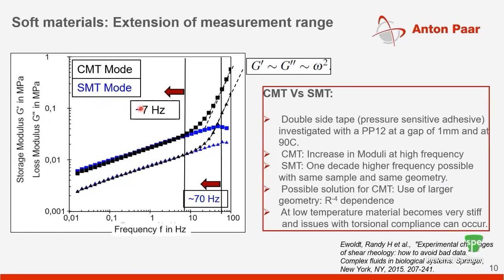And if you take a look at the black data, which is in the CMT mode, you will be tempted to interpret a curious power law scaling in the data. If you look at this increase in modulus as you increase frequency. But one needs to be careful because we know that this data at high frequency is plagued with instrument inertia, which actually is not a material property and happens a lot in CMT or control stress type rheometers.